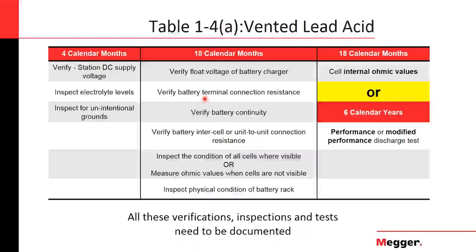It's a basic multimeter measurement. Then you need to inspect the electrolyte levels. Vented lead-acid batteries are in clear jars that you can see through, so you can inspect them and see what's going on inside the battery. And the electrolyte level is one of the most important. It evaporates with the battery operation, and you need to keep those levels up and within the specs. And another inspection that you need to run every 4 calendar months is to inspect for an unintentional ground.